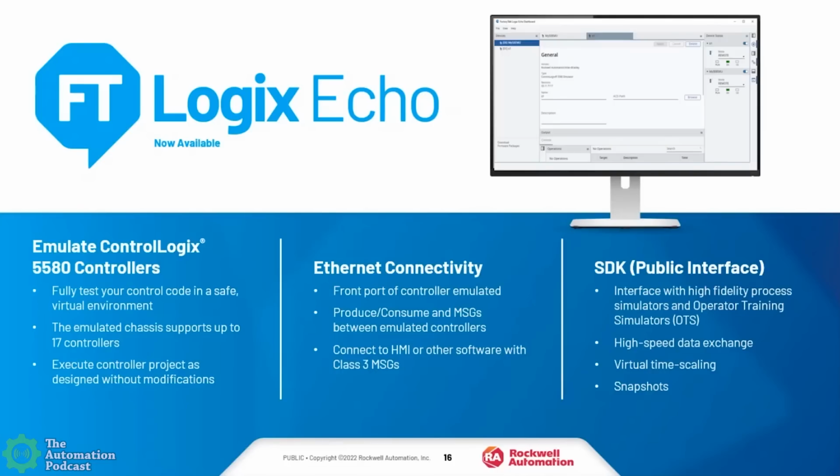So this next part is personally one of my favorites, especially coming from support. I wish I would have had this tool back when I was there, just so I wouldn't have to physically change my setup every time someone called in. It emulates the front Ethernet port of a controller, which means you can do messaging and produce/consume between emulated controllers to see how they're actually going to work before you put it onto a live line. And with that emulation of the front port, you can also connect to an HMI. So you could truly test at a system level.